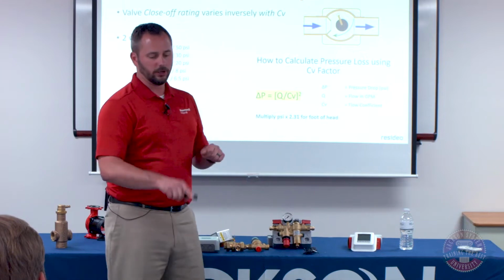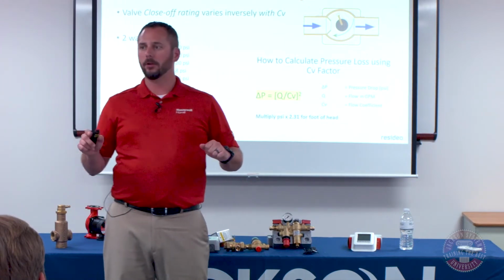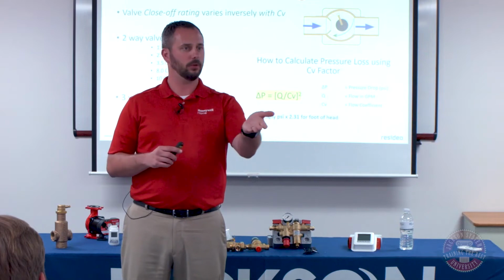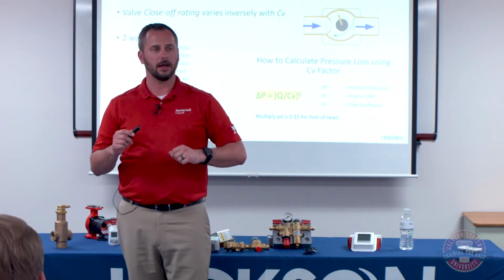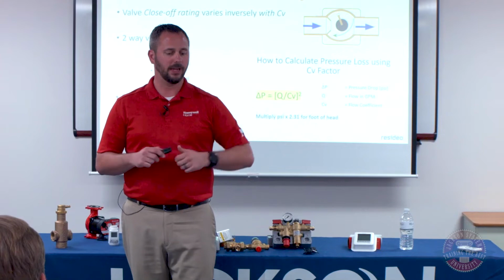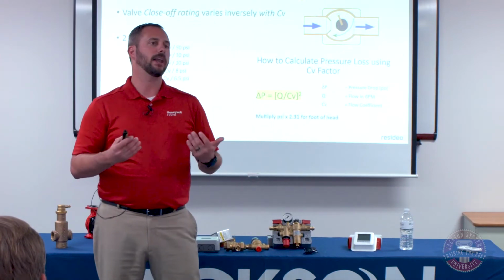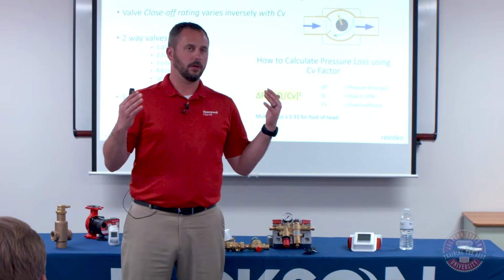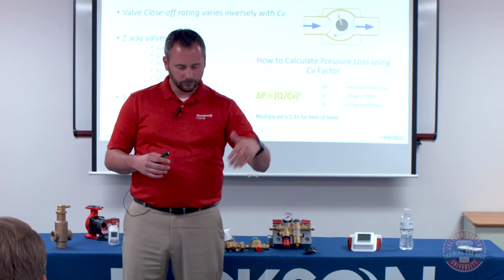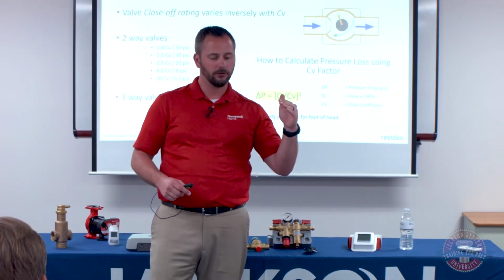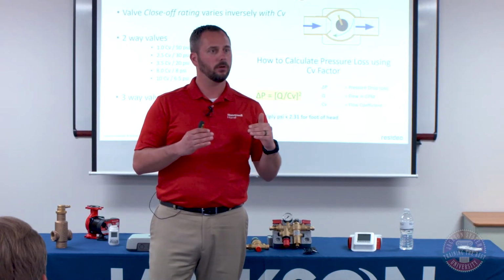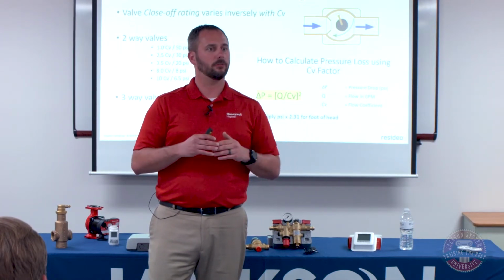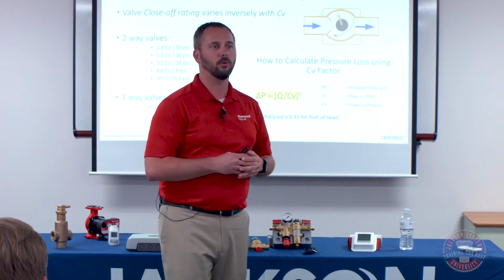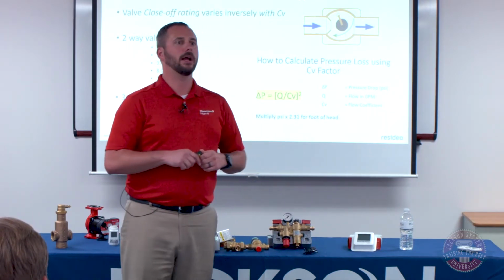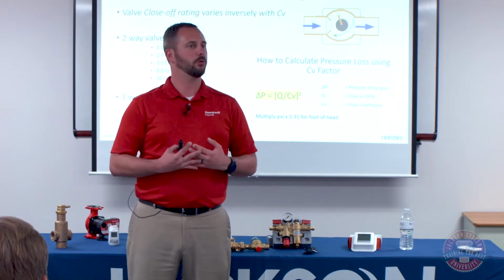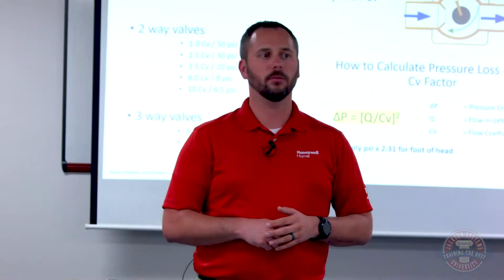And then just real quick on your CV, if you want to write this formula down, I believe you are making this available as PDFs as well. That formula is handy for finding your pressure loss. All you have to do is take your flow rate, divide it by whatever the CV rating is, and multiply it by itself. That'll give you the PSI loss through there. And then to get feet of head, you just multiply by 2.31. So if you ever need to figure out whether you're going to run up against too much pressure through a valve, just take your flow rate, divide it by the CV rating, and multiply it by itself.